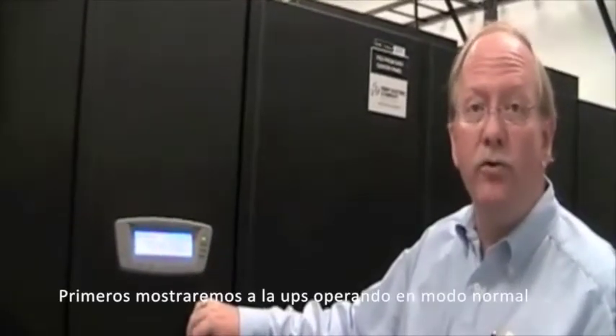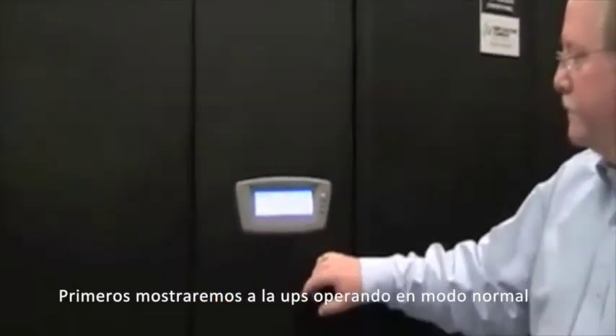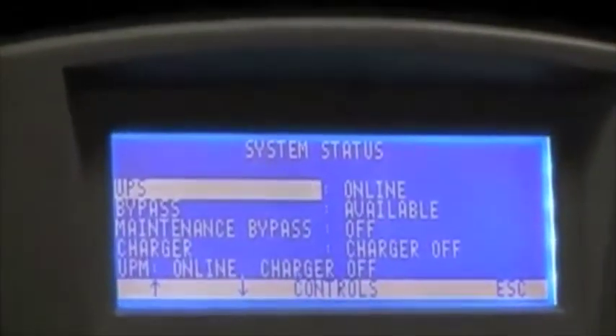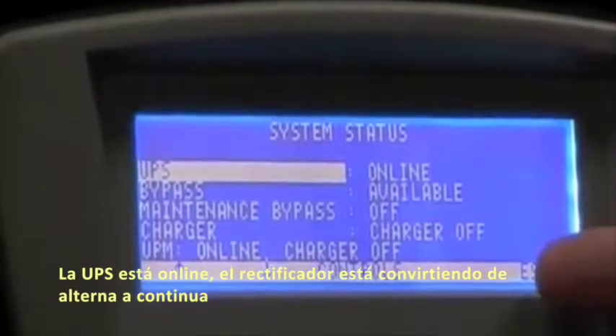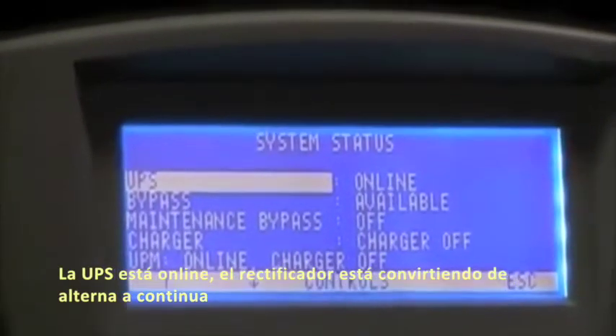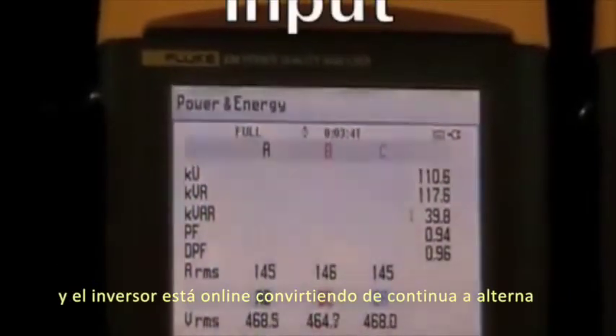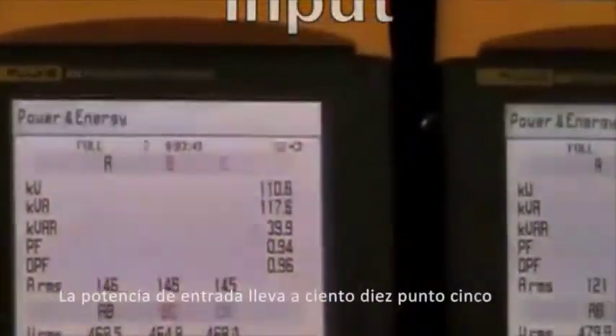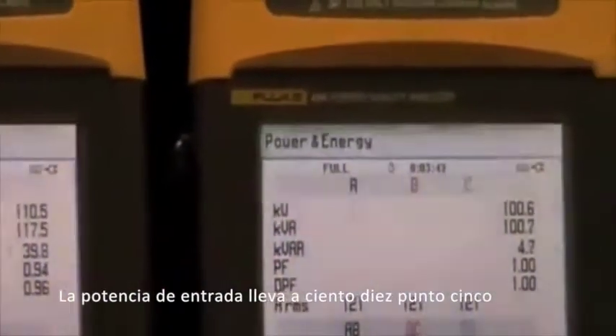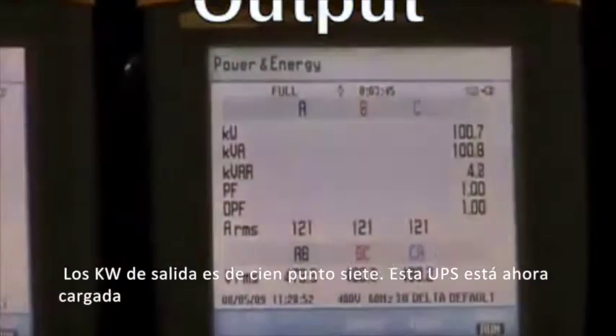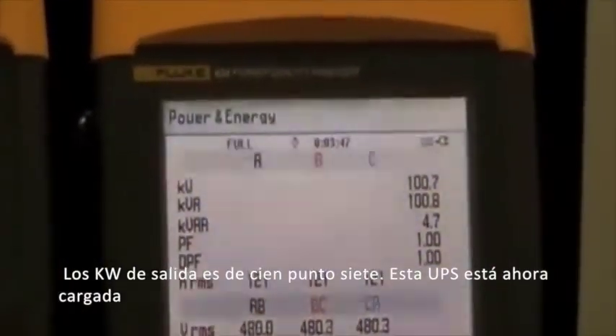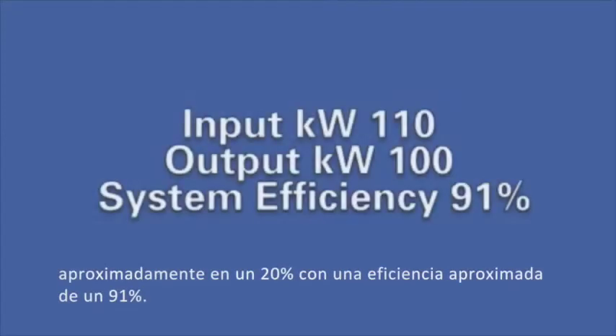The first thing we'll demonstrate is the UPS operating in normal mode. The UPS is online. The rectifier is converting AC to DC, and the inverter is online converting DC to AC. The input kilowatt draw is 110.5. The output kilowatts is 100.7. This UPS is now approximately 20% loaded for a system efficiency of 91%.